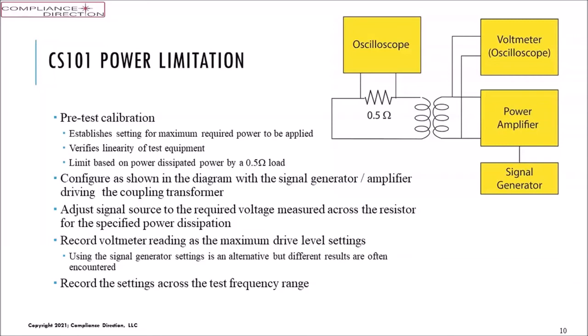Next question. How does one handle failures when they occur? Yes. Well, our target here was to discuss the calibrations, and failures in the calibration area is identifying flaws or problems with our test and measurement equipment. Something's wrong. So we need to start replacing, adjusting, verifying, and so on during the calibration checks to see what is causing it.